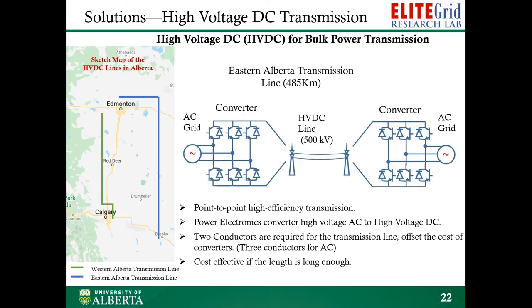Power electronic technology also helps upgrade the electricity grid nowadays. To meet increasing demands we may build large power plants, but the plant may be far from the city—for example, a hydro power plant on a large river far from the city. In this case we need to transfer bulky power over very long distances. For very long transmission lines, a DC system can be more cost effective because it only requires one or two conductors to transfer power, while an AC system requires three conductors. So for long transmission lines, DC transmission can save cost on the line, offsetting the cost of the expensive converters, making the overall system more cost effective.